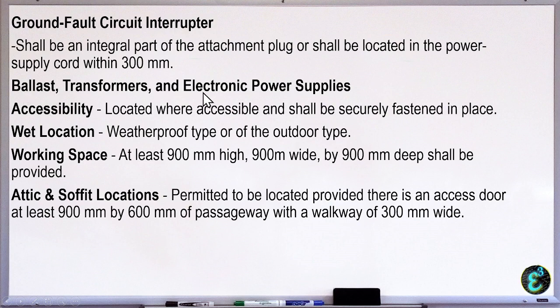Then ballast, transformer, and electronic power supplies. So the accessibility: located where accessible and shall be securely fastened in place. Kapag wet location naman, weatherproof type or of outdoor type. Then working space, at least 900 mm high, 900 mm wide by 900 mm. So ito yung minimum, 900 length, width, and height niya. Attic and soffit location, so permitted to be located provided there is an access door at least 900 mm by 600 mm of the passageway with a walkway of 300 mm wide.